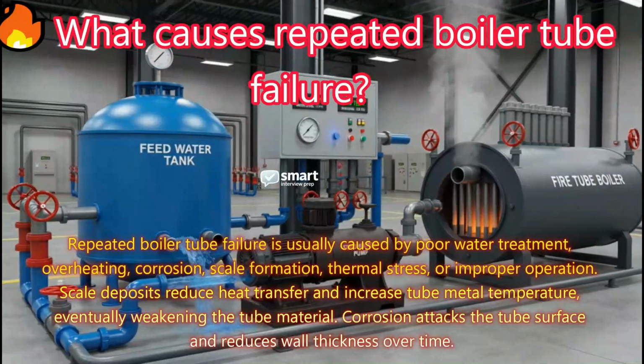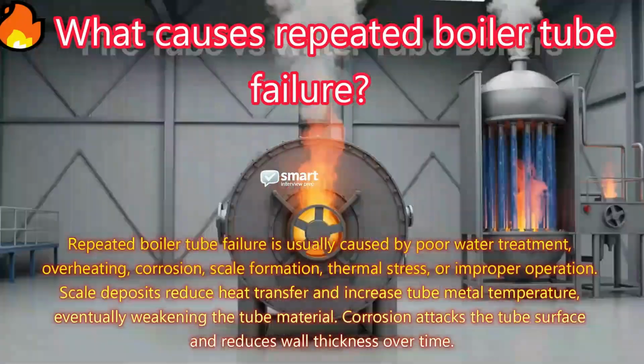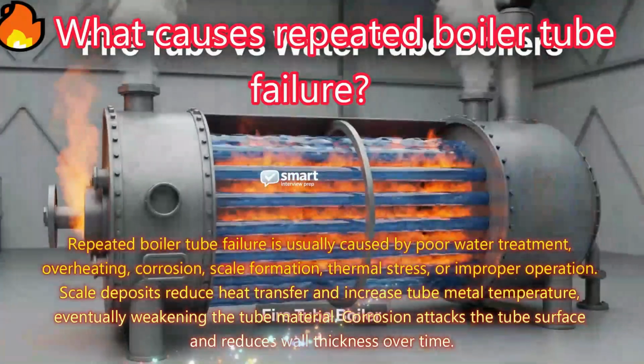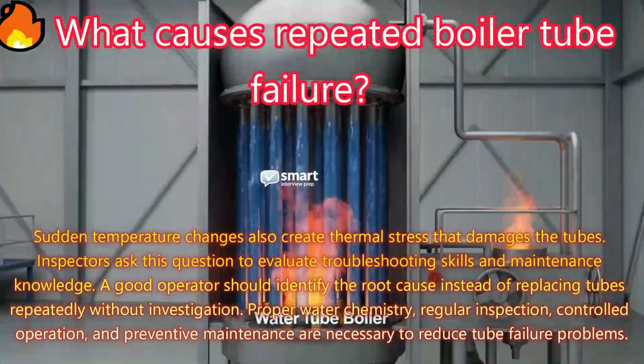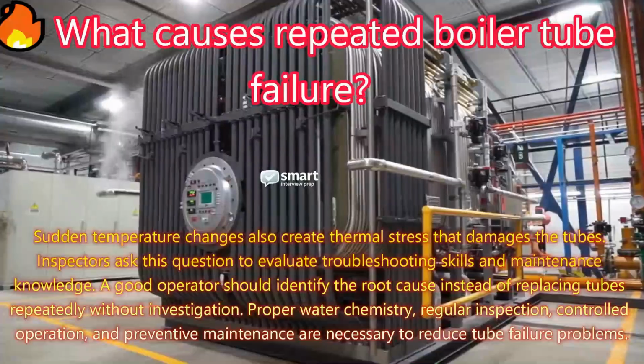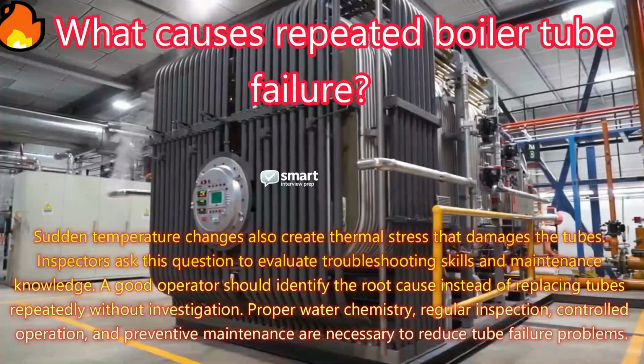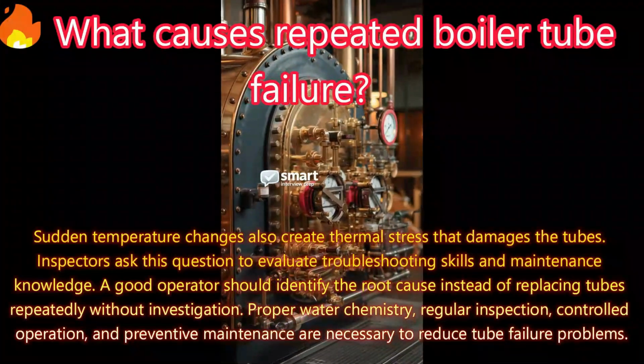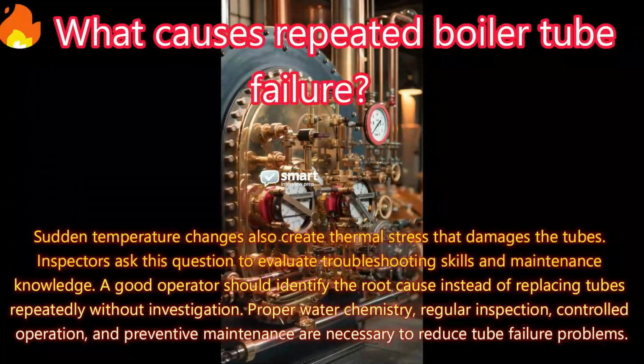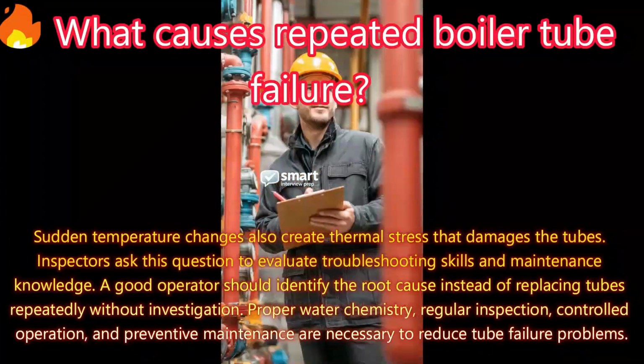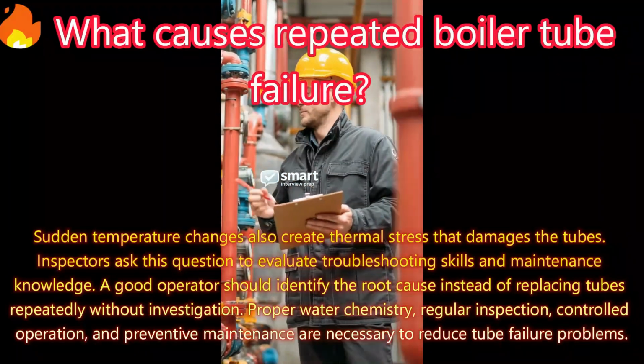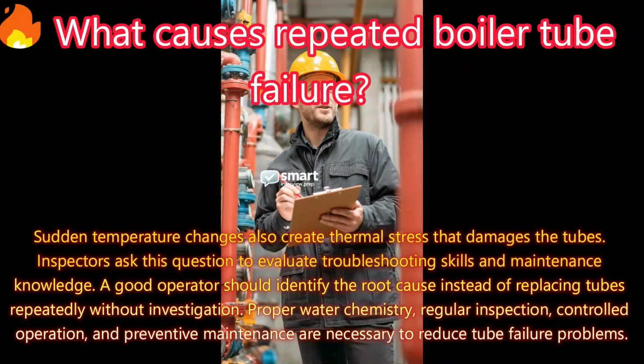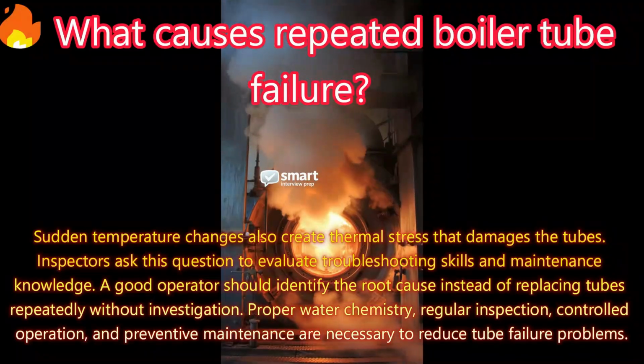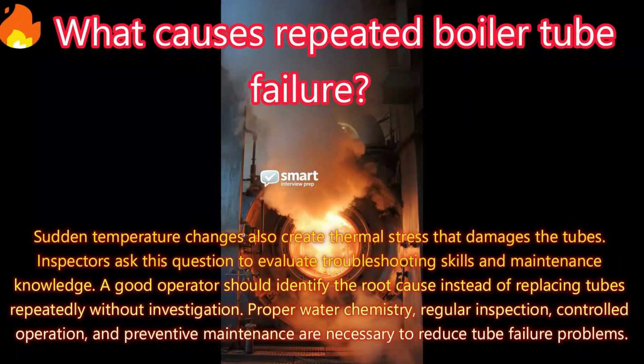Corrosion attacks the tube surface and reduces wall thickness. Over time, sudden temperature changes also create thermal stress that damages the tubes. Inspectors ask this question to evaluate troubleshooting skills and maintenance knowledge. A good operator should identify the root cause instead of replacing tubes repeatedly without investigation. Proper water chemistry, regular inspection, controlled operation, and preventive maintenance are necessary to reduce tube failure problems.